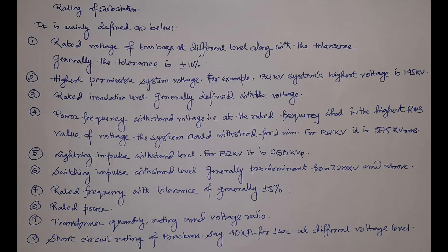Then there comes the highest permissible system voltage. For example, for a 132 kV system the highest permissible system voltage is 145 kV. For 6.6 kV it is 7.2 kV, for 11 kV it is 12 kV, and for 33 kV it is 36 kV. These are part of insulation coordination and Basic Insulation Level (BIL). I will make a separate video with a table showing the highest system voltage, lightning impulse voltage, etc. for different voltage levels.